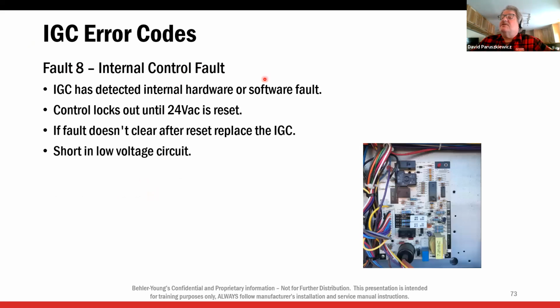Fault 8, internal control fault. The IGC has detected an internal hardware or software fault. Control locks out. If the fault is not cleared, reset or replace the IGC. If you get this fault, you probably have a low voltage short. Every time I've dealt with this one, it's been a low voltage short. I'd ask you to double check all your low voltage wiring to your gas valve. This is normally what happens.